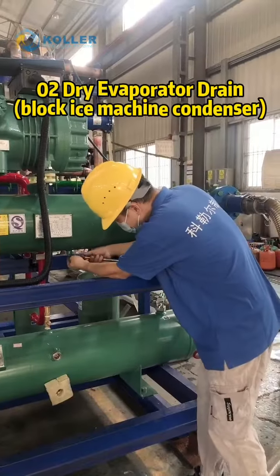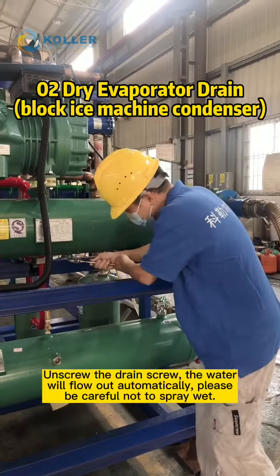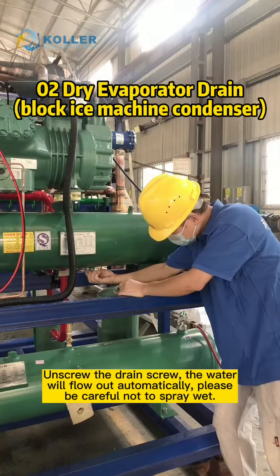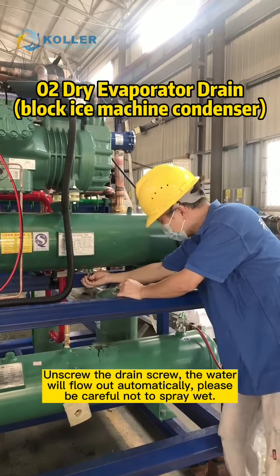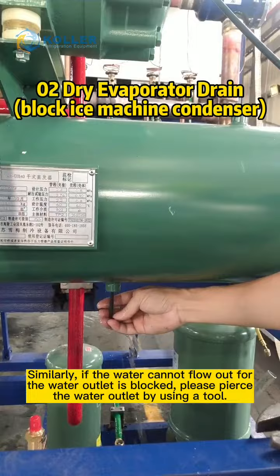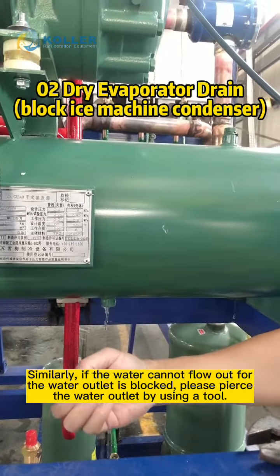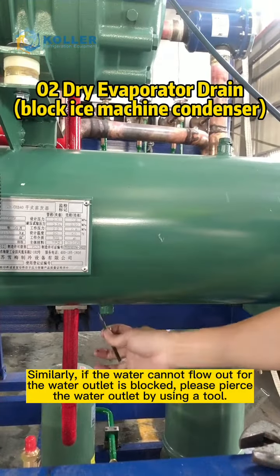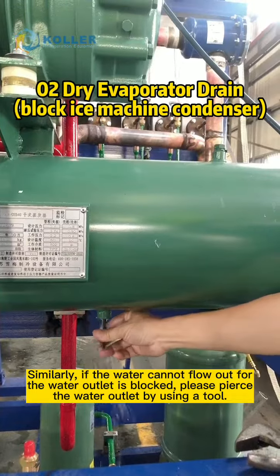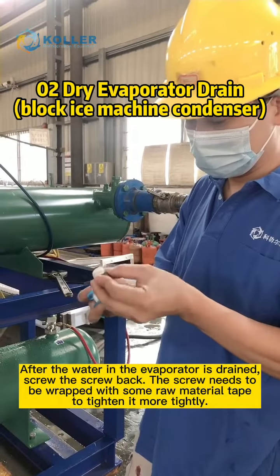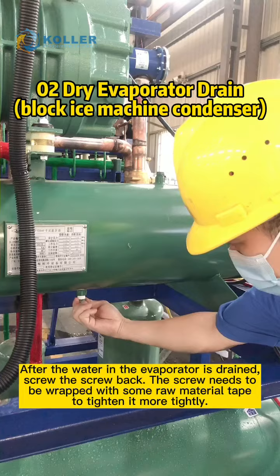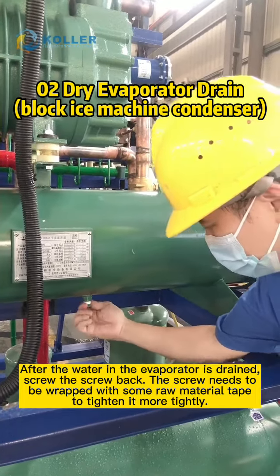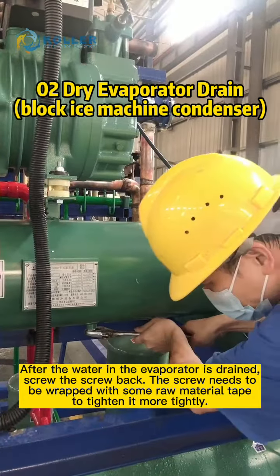2. Dry evaporator drain: block ice machine condenser. Unscrew the drain screw and the water will flow out automatically. Be careful not to get sprayed wet. Similarly, if the water cannot flow out because the outlet is blocked, pierce the water outlet with a tool. After the water in the evaporator is drained, screw the screw back on. The screw should be wrapped with some raw material tape to tighten it more securely.